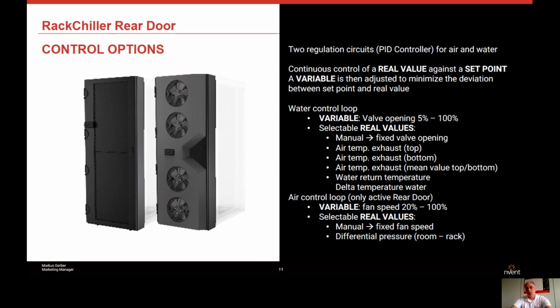To overcome this air resistance, you can add fans on the rear side, and then we suggest to regulate these fans not by temperature, but by differential pressure. So take the pressure difference inside the rack and outside in the room, and if it's becoming too high, then adjust your fan speed accordingly and support the IT equipment.